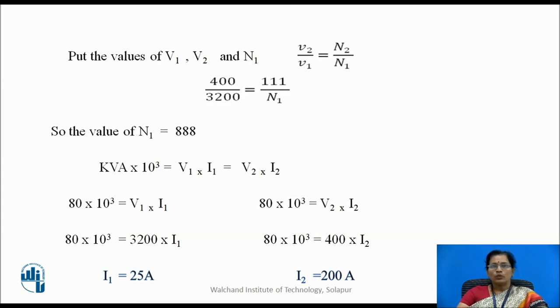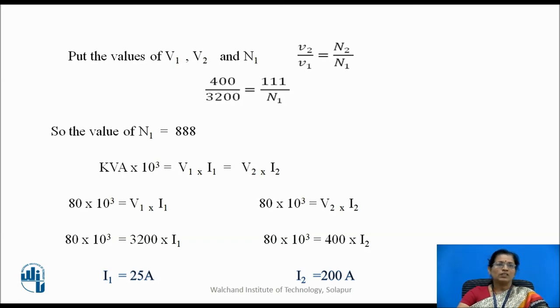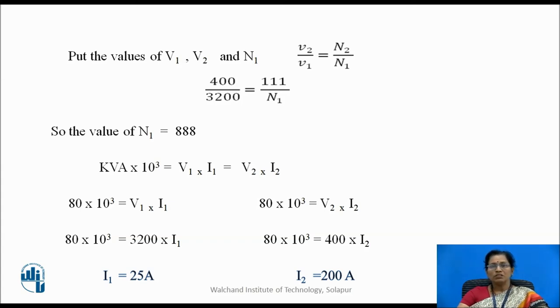Using kVA × 10³ = V1·I1 = V2·I2, we calculate I1 = 25 ampere. Using kVA × 10³ = V2·I2, substituting V2 = 400 V: 80 × 10³ = 400 × I2, giving I2 = 200 ampere.